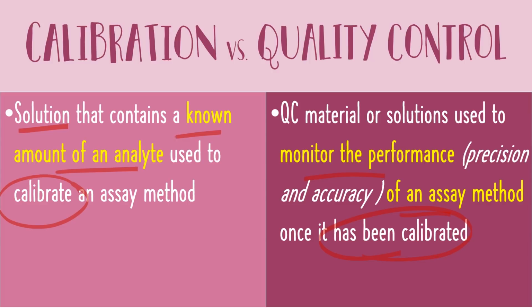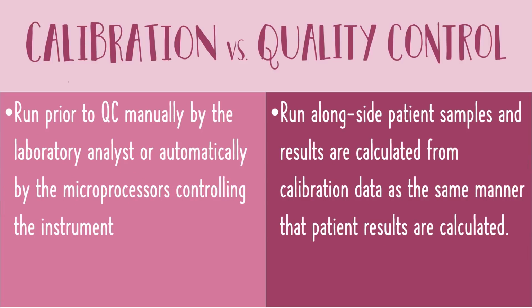So what type of performance? Mainly, if your procedure is giving precise and accurate results. So when are we going to perform calibration and running of our quality control samples? So calibration can be done manually by the laboratory analyst prior to running of our quality control samples. Or sometimes we are going to set laboratory instruments to perform automatic calibration. But most often, we are going to perform it manually so that yung calibrator natin ay hindi ma-waste, because calibrators are actually very expensive. Okay, so hindi siya dapat sayang-sayangan.